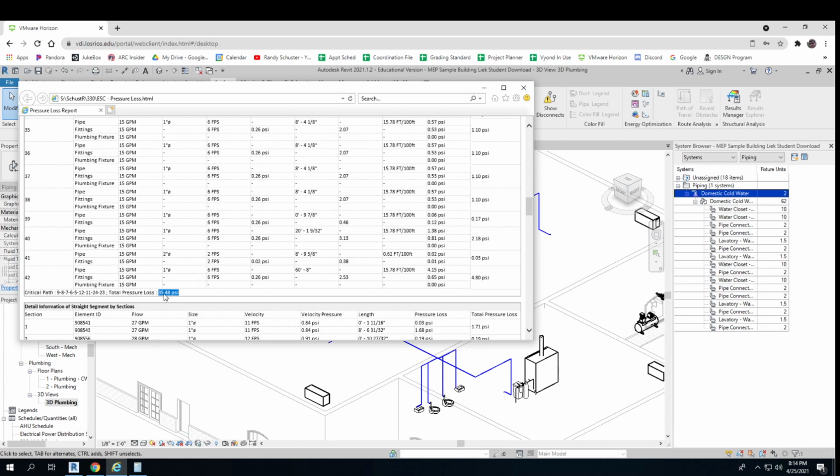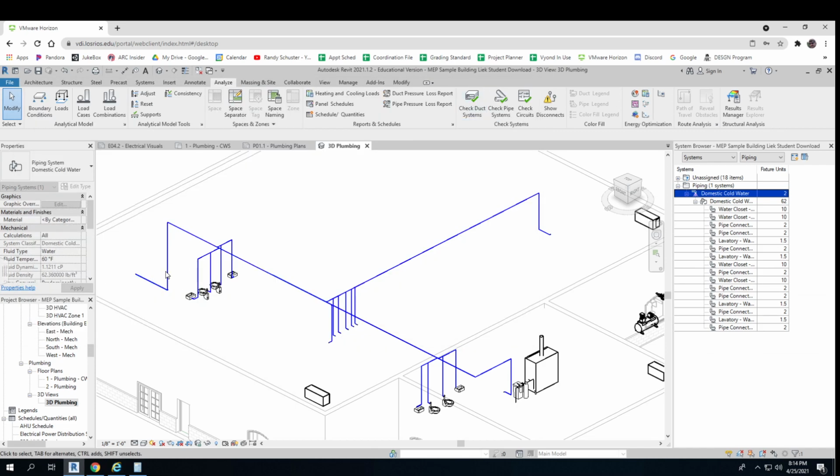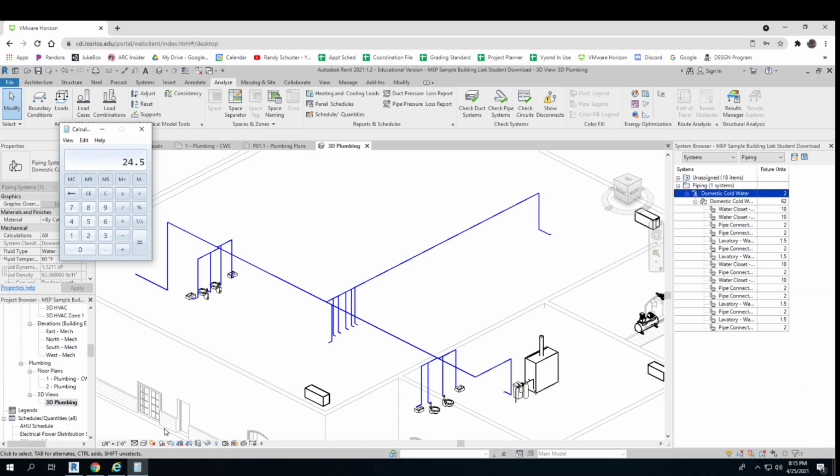And then because of all this friction loss, as the water just travels through this pipe, it gets 55, 50, 45, 40, 35. And by the time it gets to here, it's going to be 60 minus 35.5, 24.5 psi. Well, that works. It's okay. It's above 22.5. Now, some companies will make you have a little bit more margin of error than that, and some companies won't as you do your design. That's up to your engineer to tell you what to do.